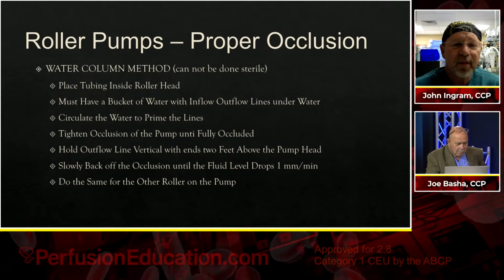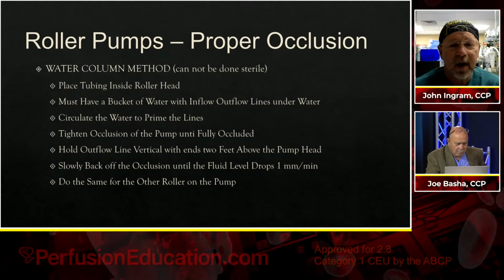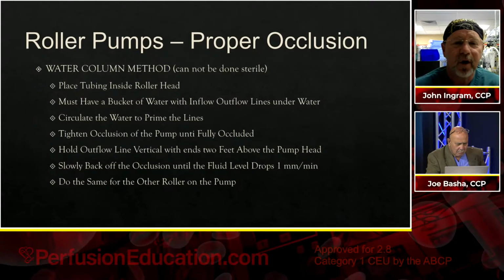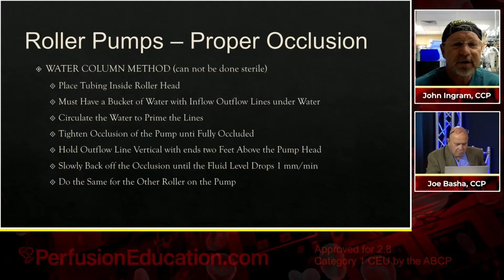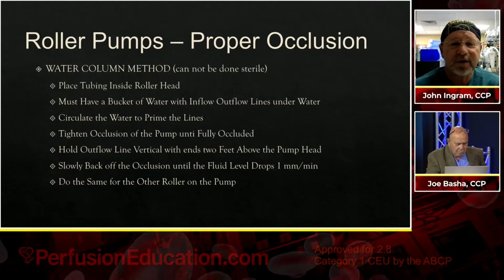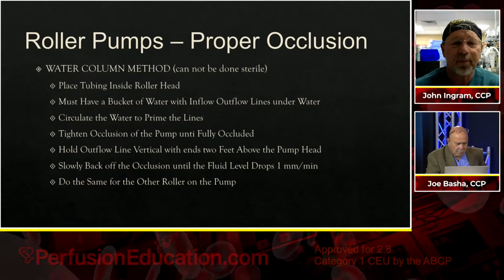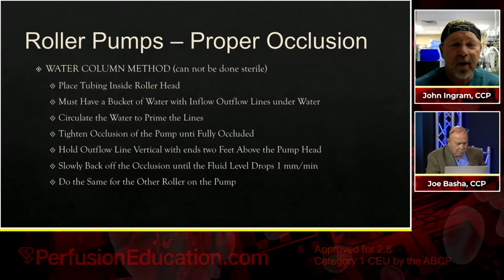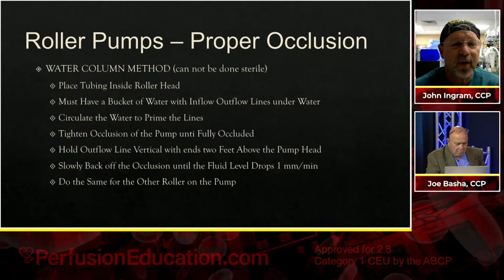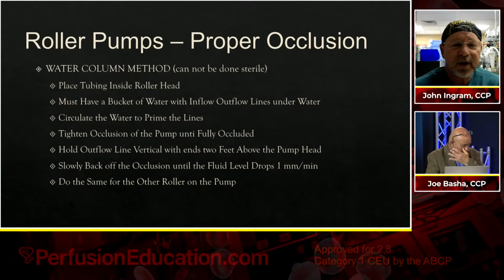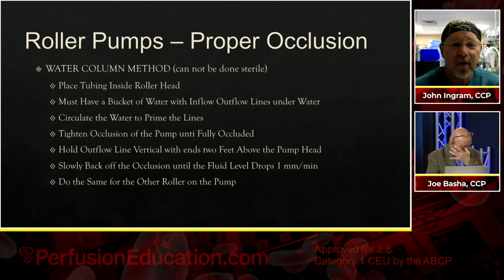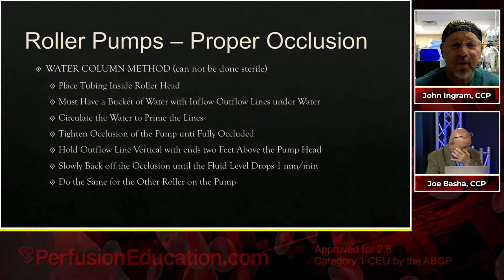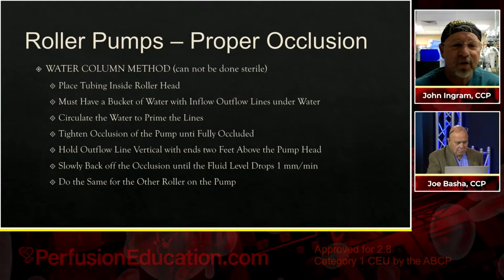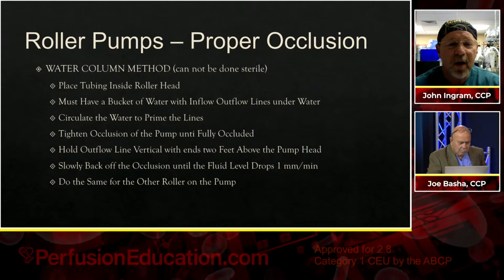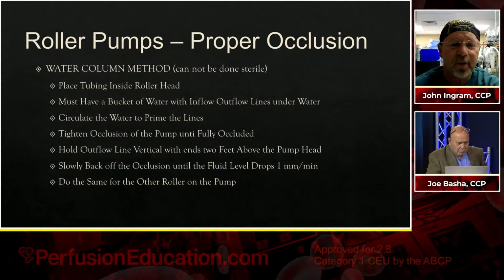The other method you can use is a water column method, and for the most part, this particular technique I'm going to show you would not be done in a sterile way. You would do this in the pump room prior to your case at some point. You place the tubing inside the roller head, you get a bucket of water, you put both the inflow line and the outflow line under the water, and you circulate the water through your prime line. So basically you've primed your tubing.